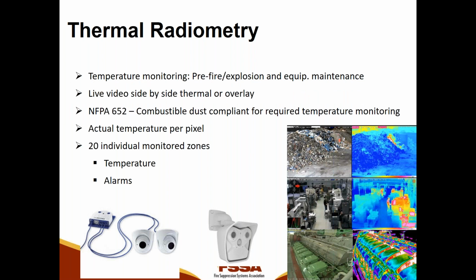So thermal radiometry can be used in those locations. So the thermal radiometry in this case is an IP camera powered over Ethernet. On the left-hand side, there are 2 thermal radiometry cameras. These are FLIR imagers connected to an IP device. So you can just run an Ethernet cable to these locations or to these detectors. A central relay is used to notify an alarm. So the alarm can be on temperature increase or temperature decrease.